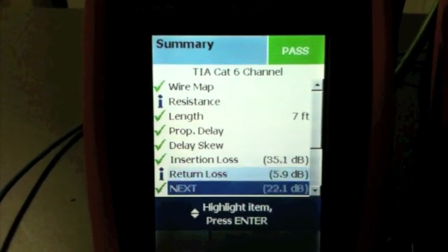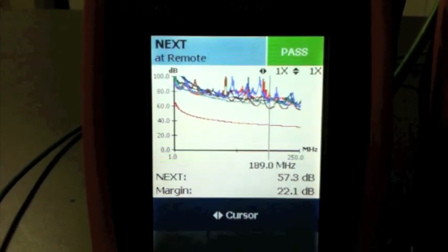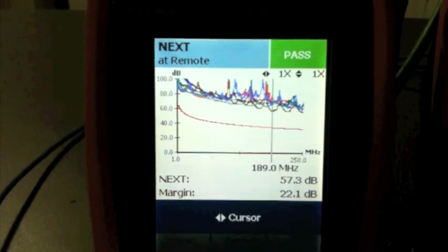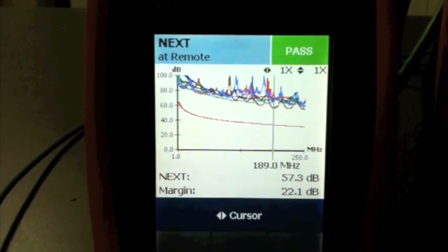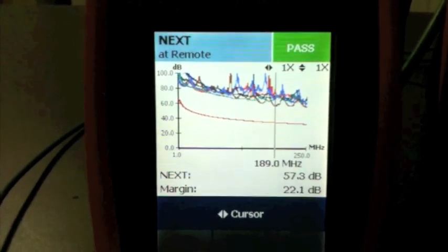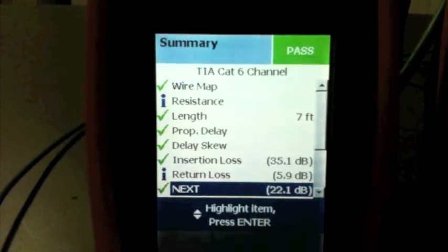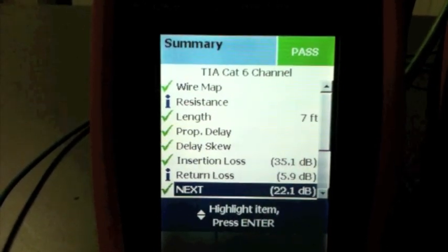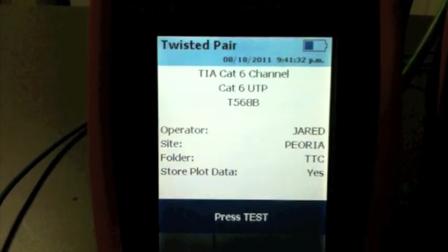Basically what we're looking for is near-end crosstalk, which is NEXT. That red line there is the failing result. As you can see, we're 22 dB above failing.